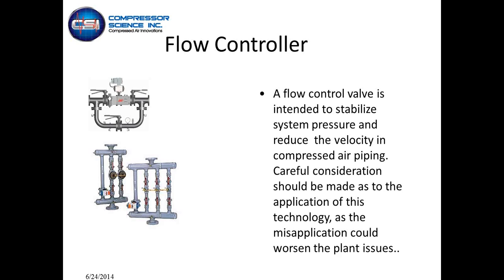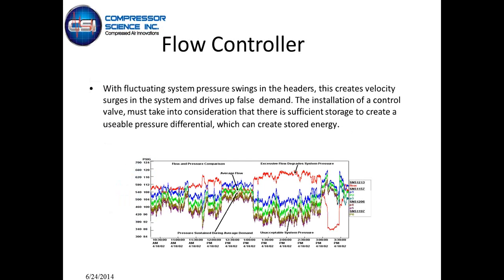If you just put in a flow control valve because someone happens to sell it and they have access to it, where we've seen these things bypassed because they don't work is because there wasn't sufficient storage or there wasn't enough differential on storage in order to maintain proper downstream pressure, and they just get bypassed and people say they don't work. They do work in the right application. Again, the idea is with fluctuations in the swings of the header, but you've got to have usable differential and you've got to create that stored energy. If you can't, it's not worth putting it in.